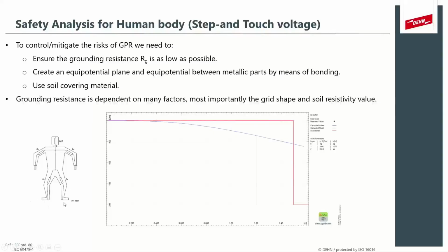This is to ensure insulation between the human body and the actual ground potential rise. And it just adds to an insulation level on the grounding level. So as I mentioned, the grounding resistance is dependent on a lot of factors. You can change the grounding resistance by changing the grid shape, material, and the soil resistivity. So you can also enhance the soil conditions. This graph is also calculated using XGSLab software from a lot of field measurements.